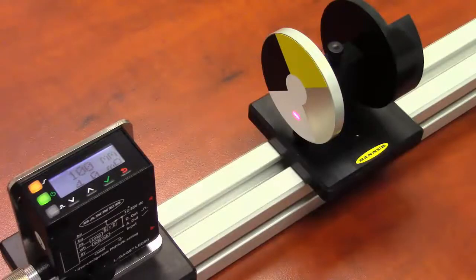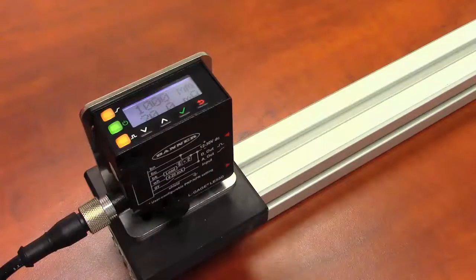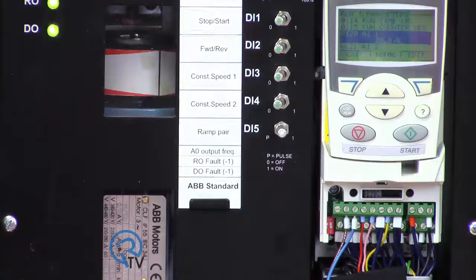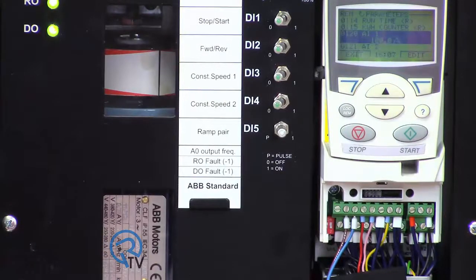With default settings, the sensor provides a 4 milliamp output at 100 millimeters and a 20 milliamp output at 1000 millimeters. Based on a percentage of full scale, we can confirm these readings with the drive. Again, 100 millimeters should be 4 milliamps and 1000 millimeters should be 20 milliamps.